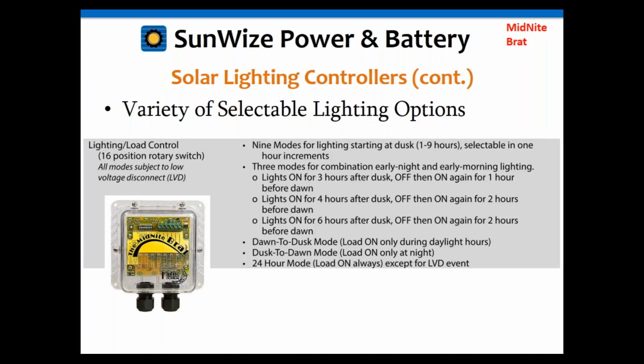2 hours. The lighting starting at dusk typically will turn on at dusk and then just remain on continuously until dawn. So basically a night light function, where as soon as it senses that it's dark out, it powers on the lighting load and then turns off when it gets light out again.